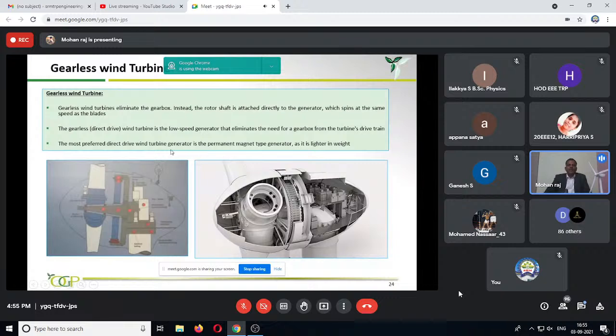The most preferred direct drive wind turbine generators are the permanent magnet type, as it is lighter in weight. Because the weight is very low, the permanent magnet is the most preferred in the wind industry. You see, I have told you that this is the blade which is mounted. This is a cross section of the direct drive turbine.